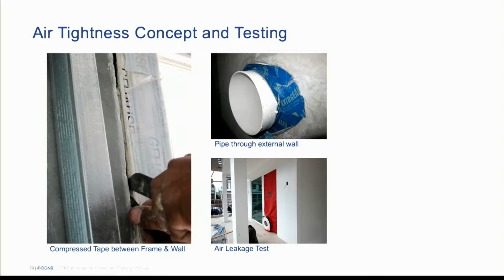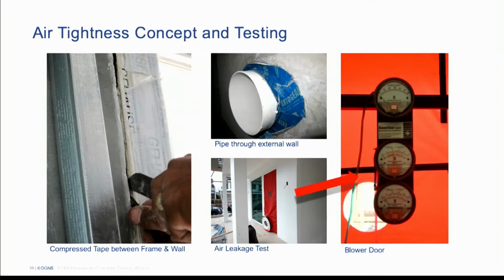Then we conducted a blower door test: we produced a pressure difference between inside and outside, measured how much air goes through the ventilator, and from that determined the air leakage rate of the building. This is a European and American technology to measure building leakage, and the nice thing is that this building would fulfill German requirements, so it's a very airtight building.